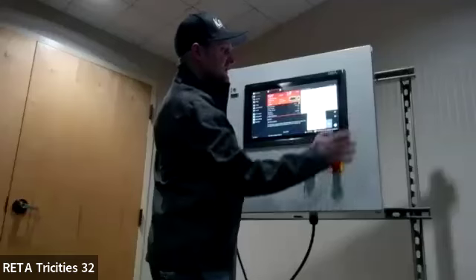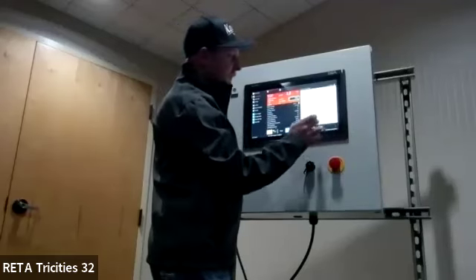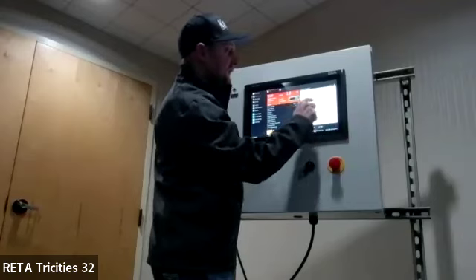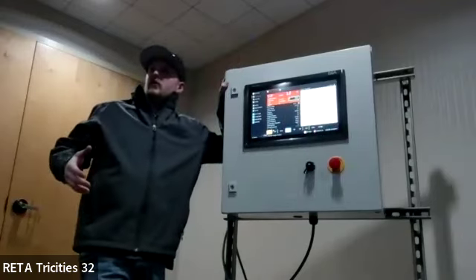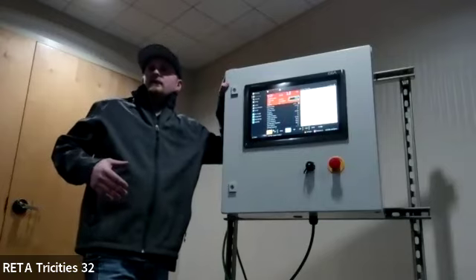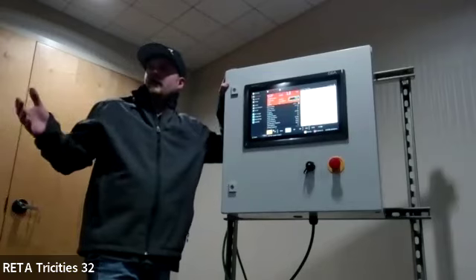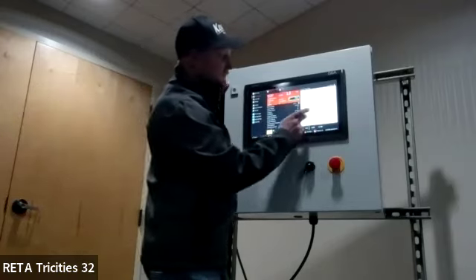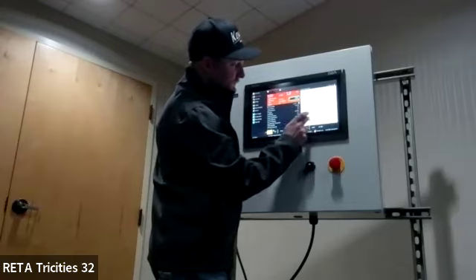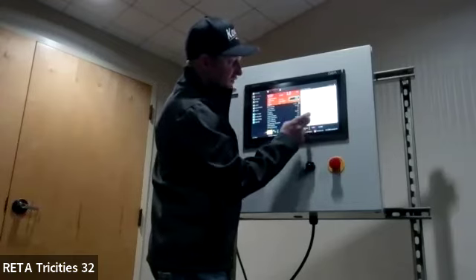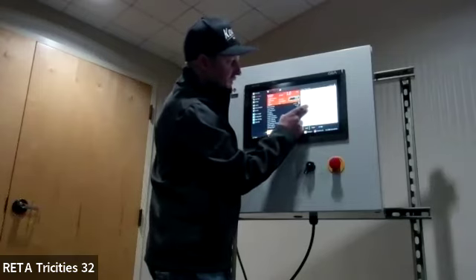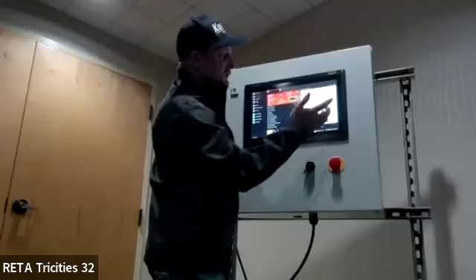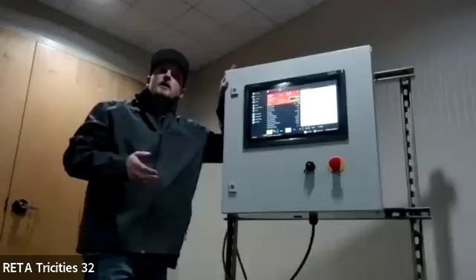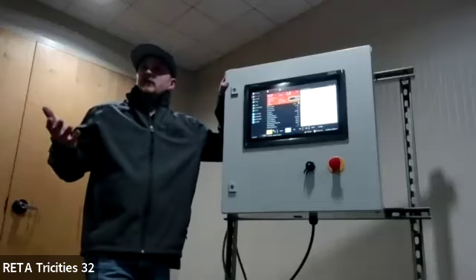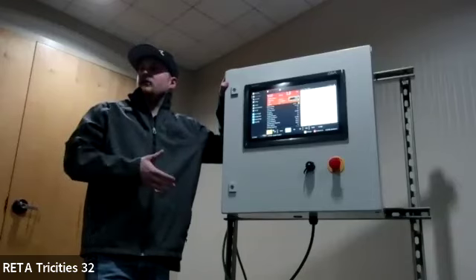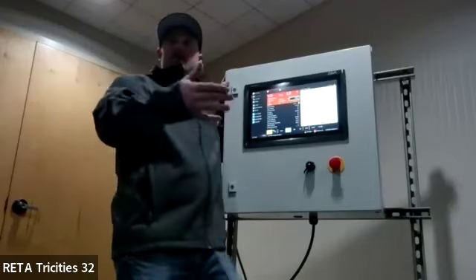You can do set point location is local or remote. These actually have the opportunity to start from a digital signal also. You don't have to have it, you could have your control system set a digital start stop command. You just have to enable that. Minimum capacity slide allowed to start. You can have it to where the sequencer overrides local capacity parameters. Let's say you're running like a Logix system. Logix is going to override your capacity control parameters from their stager.